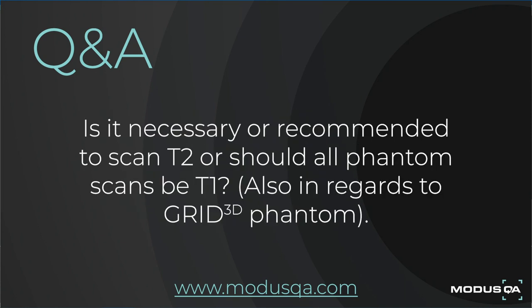Eric's question is: is it necessary or recommended to scan T2, or should all phantom scans be T1, also in regard to the GRID3D phantom? We do support both T1 and T2 weighted. T2 weighted scans can be very long if the parameters are chosen to be heavily T2 weighted. For regular QA, the worst case is a T1 gradient echo sequence, which is very fast. It is usually advised to use your worst-case type of scan if it can be acquired in five minutes versus a 20 or 40 minute scan. If you do have time for periodic QA, T2 scans can also be analyzed.